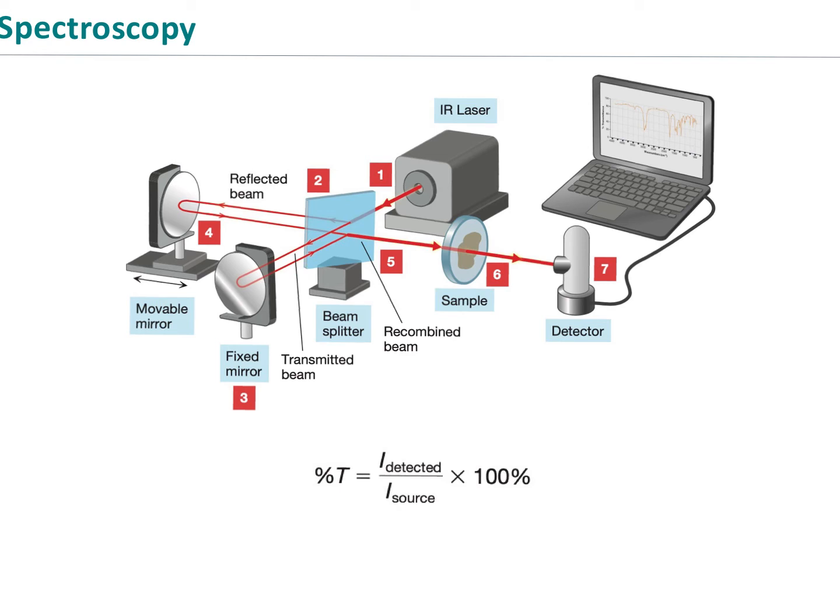Now, that transmitted beam, as we mentioned, goes towards the fixed mirror, and then the reflected portion is guided back by a movable mirror. That's a mirror that's movable within the instrument. They're guided back here. If you follow the arrows, it goes bzoop, bzoop, bzoop, to where it gets really dark here. And then this one goes zoop, and back, to where it gets really dark here. The sound effects are completely optional, but it does make it more fun.